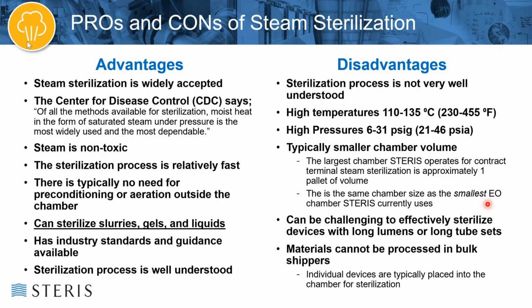So up here where I said the smallest EO chamber is roughly a pallet size, in that chamber they can literally drop a pallet into the chamber, and on that pallet will be 10, 20, or 30 cardboard shipper cases full of product. And you can just simply process it that way. You put it in the chamber, you pull it out of the chamber that way. With steam sterilization, you cannot process the cardboard shipper. And you also can't process, in most cases, a shelf box. So the individual devices in their primary sterile barrier need to be taken out of all of the packaging. And then in most cases, they're individually loaded into the chamber, which is very time consuming and labor intensive. And then they're processed that way, and then everything has to get repackaged before it's sent back to the customer. So that's definitely one of the disadvantages to consider.